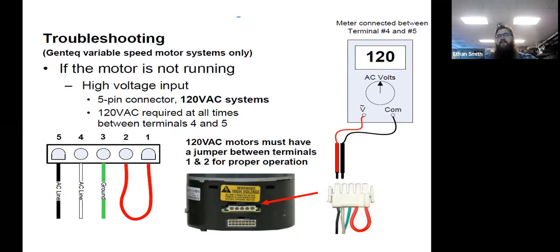So the first thing to test on a variable speed motor is the high voltage input. This is the harness that you'll see inside a furnace typically. Inside an air handler, it's still going to be a 5-pin, but there's not going to be that jumper in there. That jumper tells this motor whether it's being fed by 120 volts or 230 volts. So in the air handlers, you'll have this jumper removed. In the furnace, that jumper will be there. But these motors are actually receiving 120 volts all the time in the furnaces and air handlers. So they should always have 120 volts to that motor. So that's the first thing to check. If we don't have high voltage, the motor's not going to run.